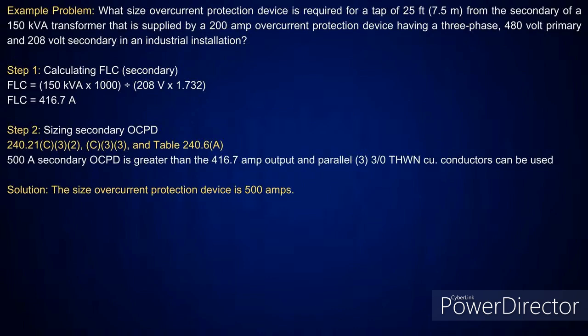So I have a 150 kVA transformer, take it at 1,000, and then you're going to divide it to get your amperage, just like we did when we first started this Master and Journeyman class. What did we cover? How to apply these formulas for sizing your amperage when we were doing kVA. So I've got a 208 volt secondary, three phase, 1.732 for the three phase. That'll be 360 volts. Divide that in, gives you 416.7 amps.